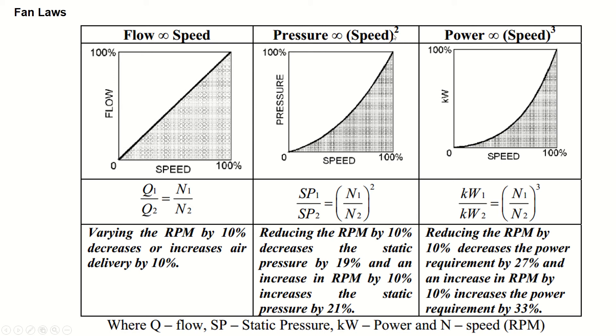The second fan law states that pressure is directly proportional to the square of RPM. This means that reducing RPM by 10% decreases pressure by 19%, while increasing RPM by 10% increases pressure by 21%.